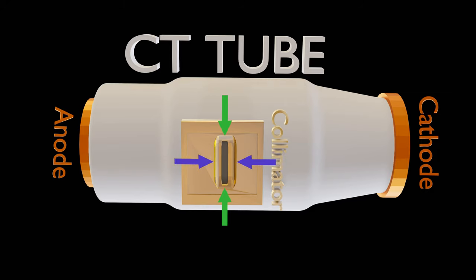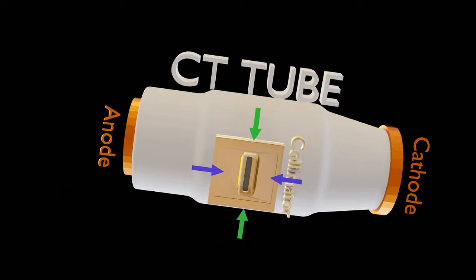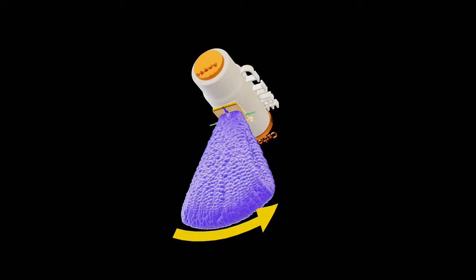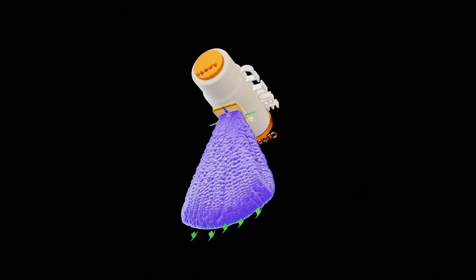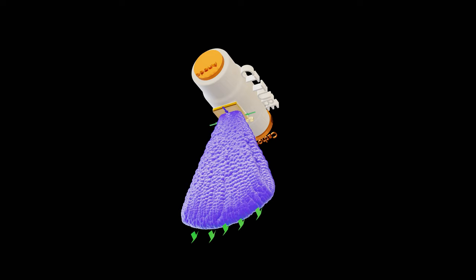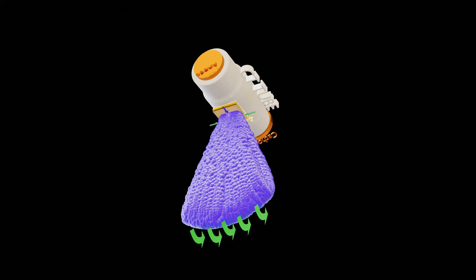This collimator has shorter opening along anode cathode direction and wider opening in perpendicular direction. The fan beam generated from this tube will not have heel effect along wide fan angle. It rather will be present in shorter beam direction or patient z-axis. This orientation eliminates heel effect induced spectral changes along the fan angle, which is important for better image quality.